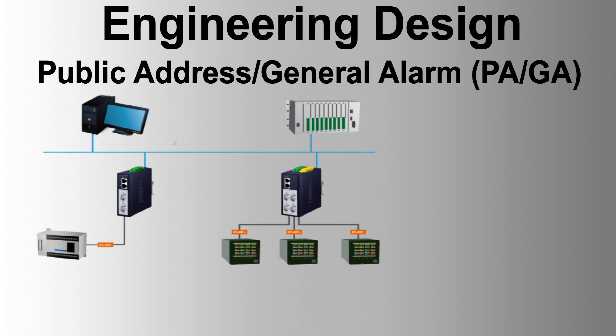PAGA sound levels: designed to provide even sound diffusion audible over background noise levels. The signal-to-ambient noise ratio exceeds 6 dB but is no greater than 20 dB above ambient noise. Office locations maintain sound distribution within 3 dB variation at 1.8 meters height. Areas with ambient sound levels above 80 dBA are equipped with visual beacons. Sound pressure level is limited to 124 dBA at any point between ground level and 2.4 meters height.